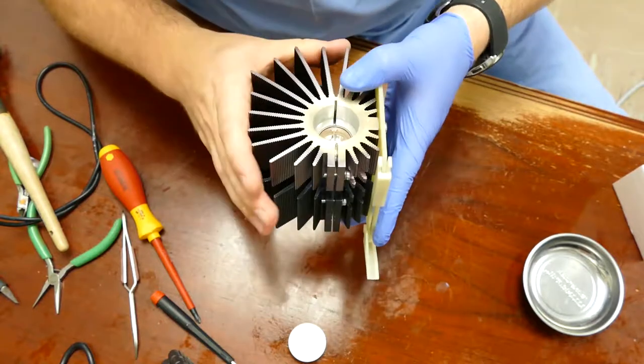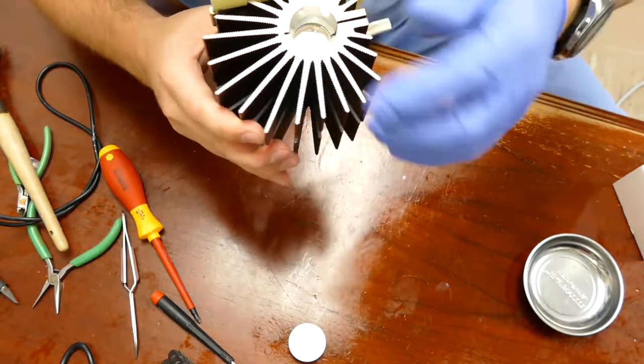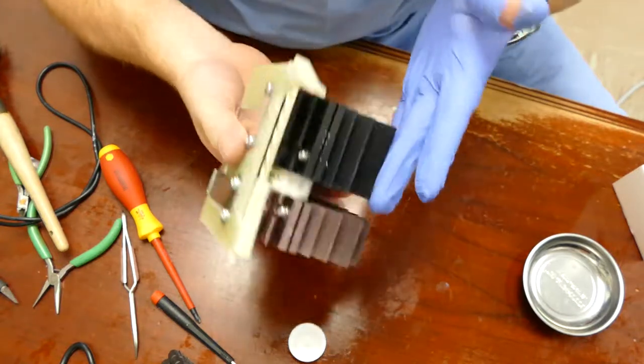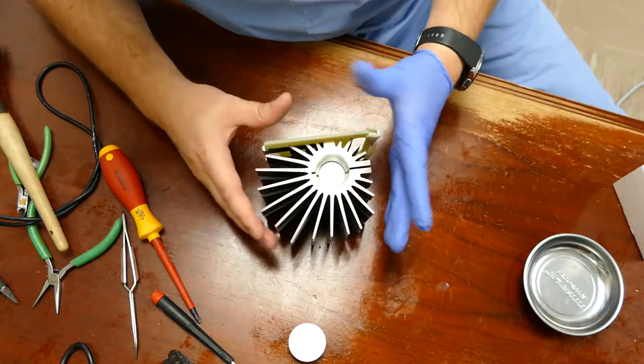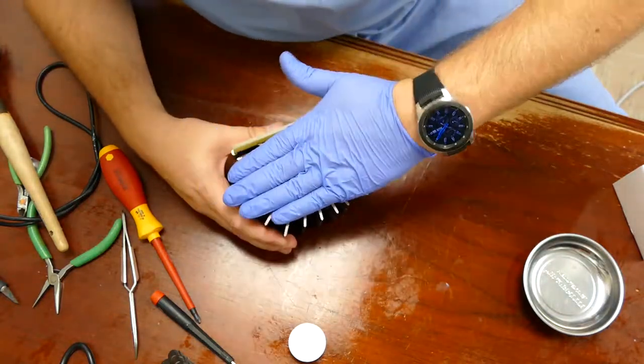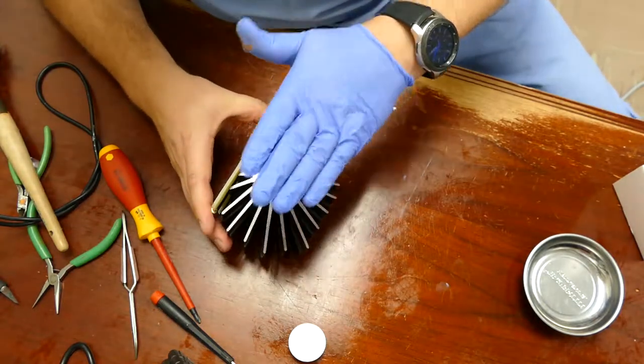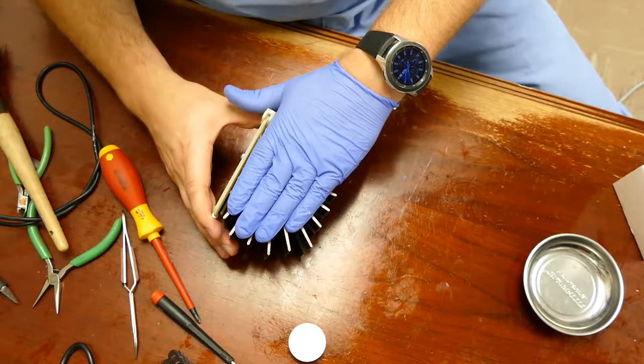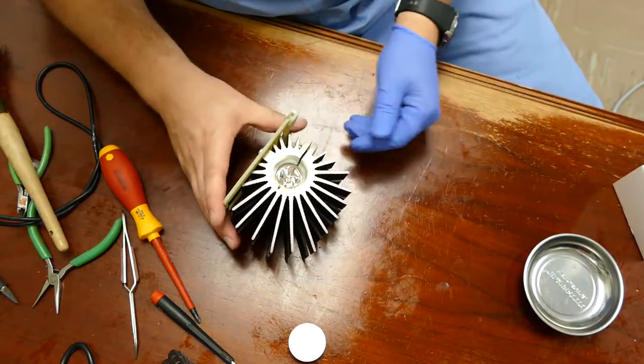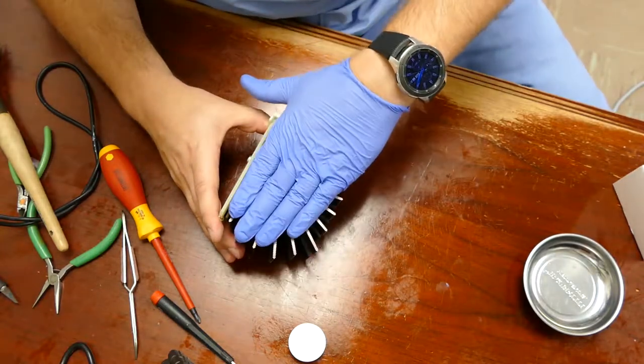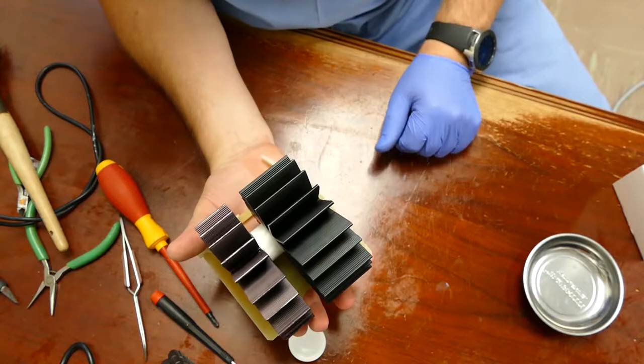My heat sink is clean and there's no debris on the lens. Alright. And that is a successfully rebuilt Karl Storz bulb. Got a little bit of compound there on the heat sink so I'll clean that off. There we go. It's ready to install. Now if you're going to put these in storage and you're just going to leave them rebuilt on a shelf, I highly suggest putting a large piece of packing tape and leave a flag off the side, because I've before, when it was just me rebuilding these, I'd put tape over the entrance, and I've had a technician install that bulb into a unit and it caused a little burn hole in the plastic. It created a little bit of a situation because he forgot to take the tape off. So now I put tape across the whole heat sink and I leave a nice 3 or 4 inch flag off the side, and that will go on the shelf as a bulb rebuilt ready to install.